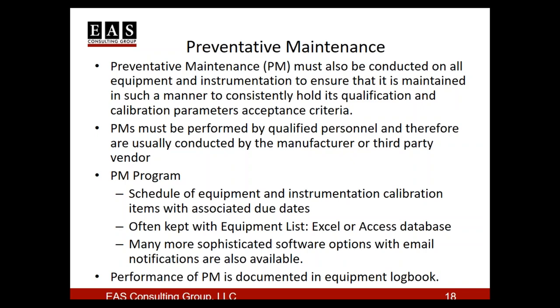So this is a system you have to track - all those time periods dictated in the SOPs that we have to do this on 3 months, 6 months, or annually, whatever the requirement is. Somebody has to keep track of that, typically in this PM program, to make sure those things are being done. Certainly analysts and microbiologists, every time they use a piece of equipment, should be looking at that and verifying it's in calibration so they can continue to use it. But you don't want it to say, oh, it's not, I can't use it today, and then they can't do that analysis. So you want a PM program that's monitoring that.